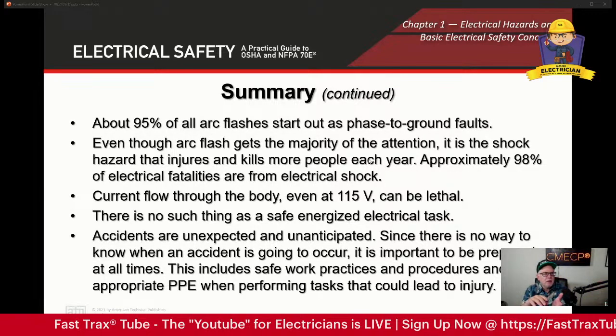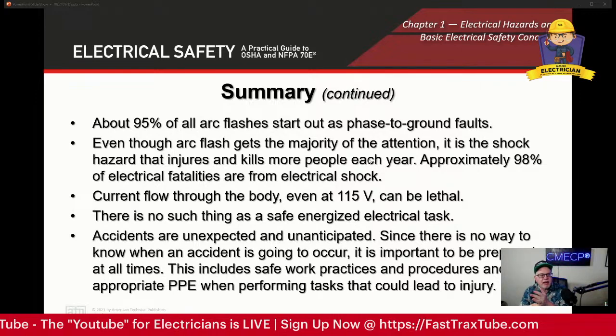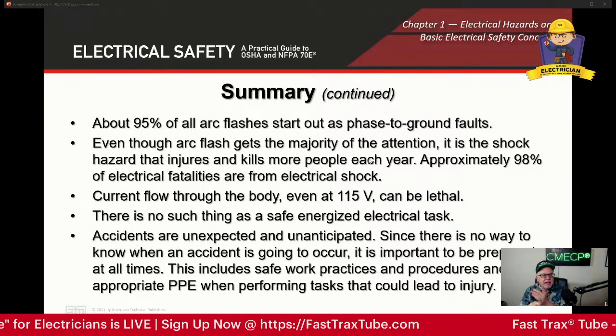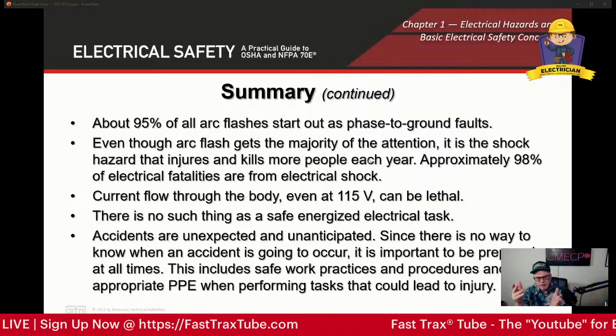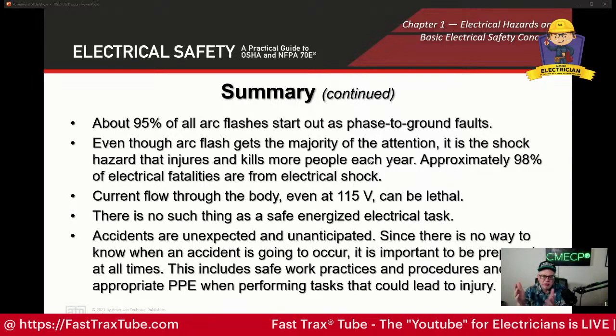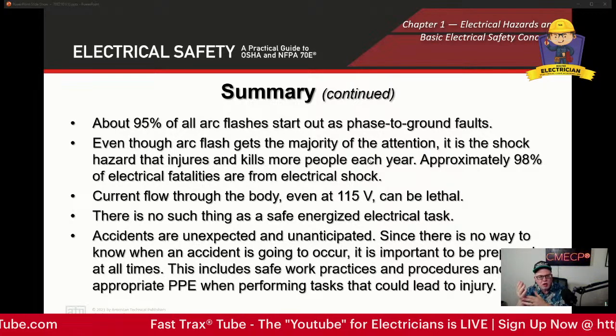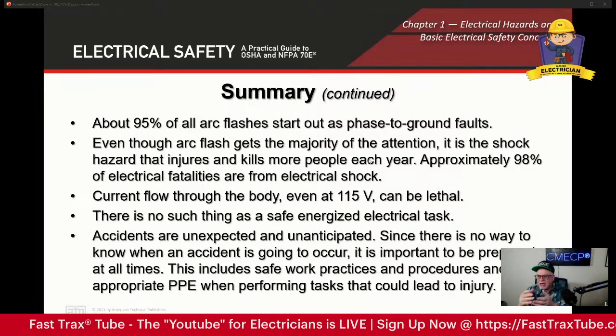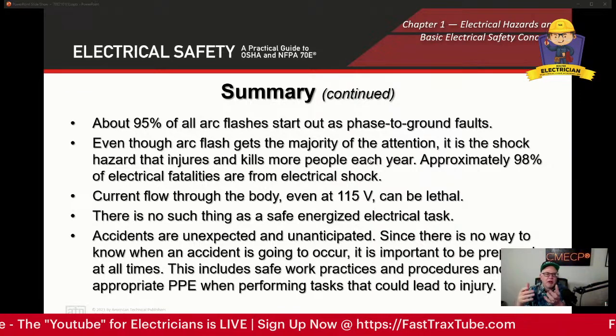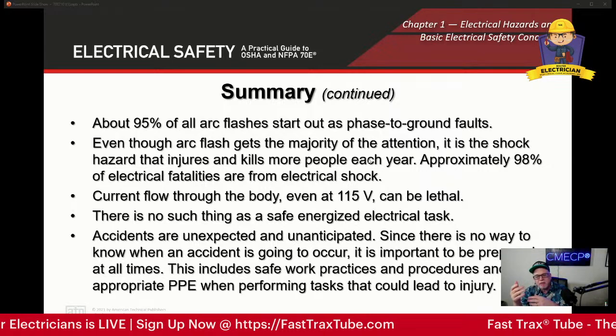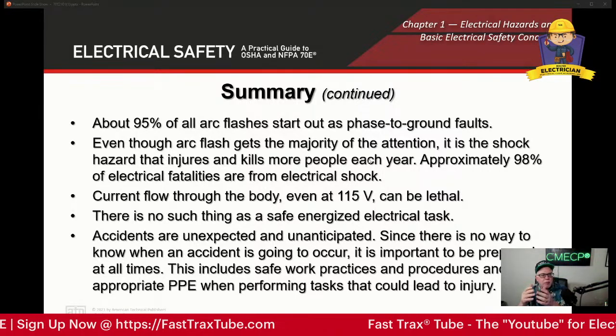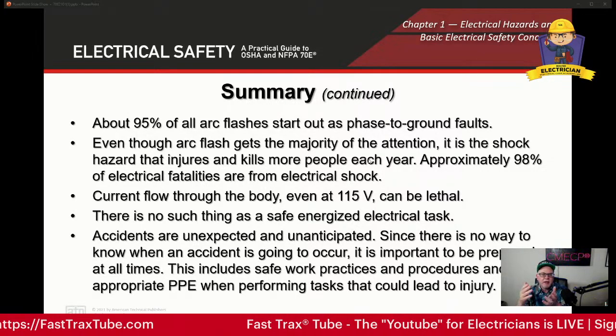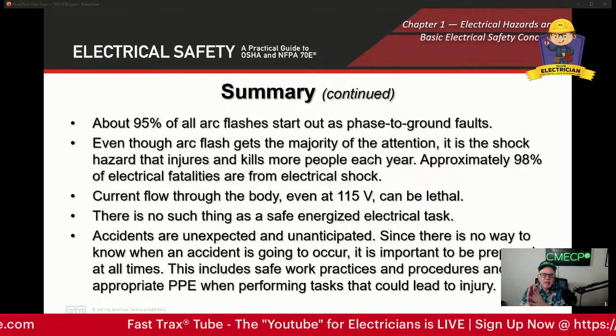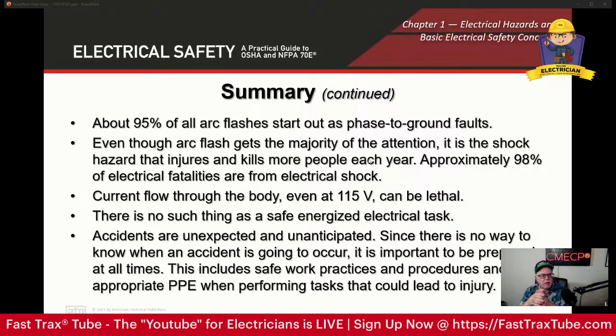Right now, about 95% of all arc flashes start out as phase-to-ground faults. Just any of the phases faulting out to ground. Maybe the insulation is worn off, maybe somebody put a clamp on too tight, maybe somebody didn't install a conductor properly, or didn't torque it right and it came loose and contacted a grounded part. 95% of those arc flashes start out as a phase-to-ground fault.